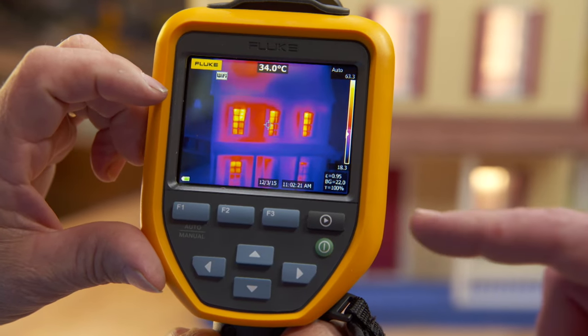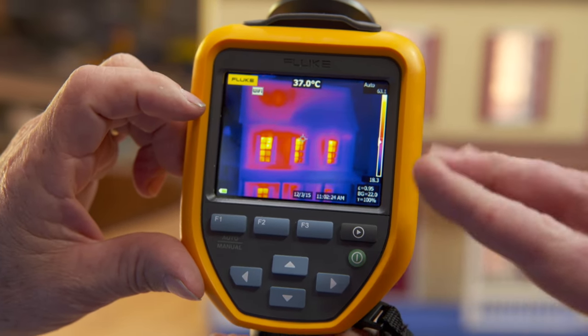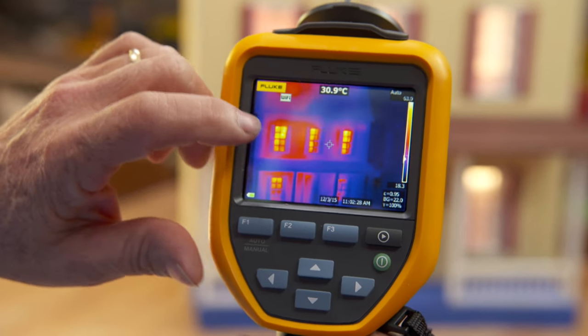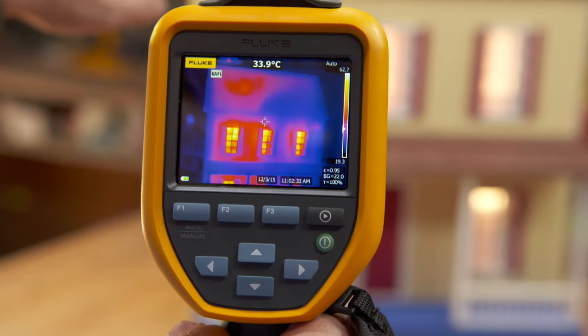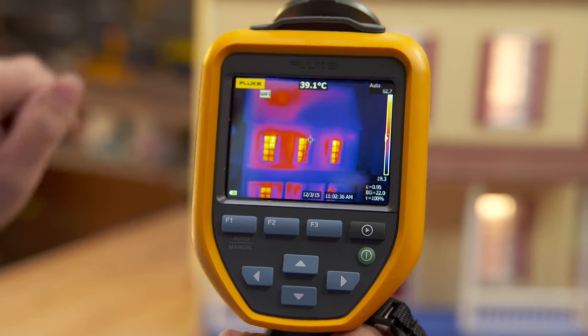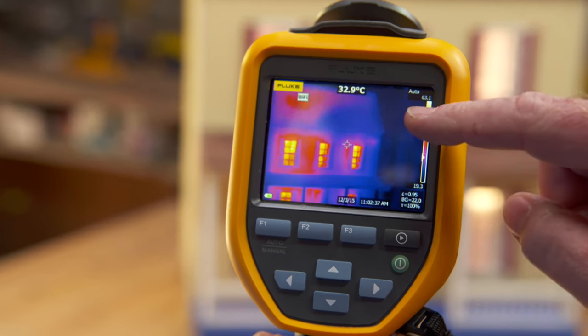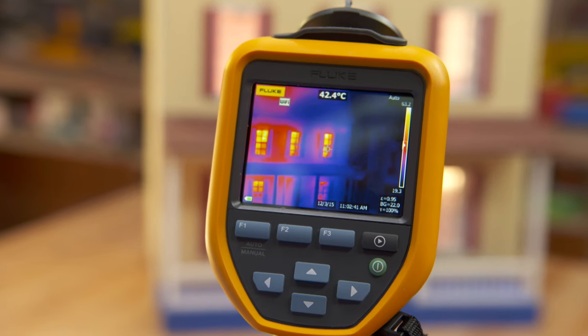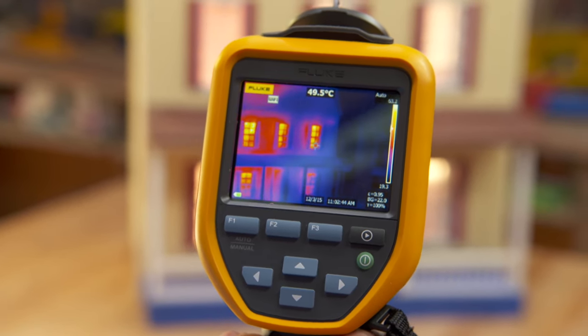On this, heat is represented by the orangey colors and cooler temperatures are represented by blue. The bright colors show the windows have a tremendous amount of heat loss. On the left side, you can see the wall and the roof is really bright, so there's heat loss on that side. Over here on the right side, the roof is kind of blue, telling us the heat is not escaping from the right — it's really escaping from the left.